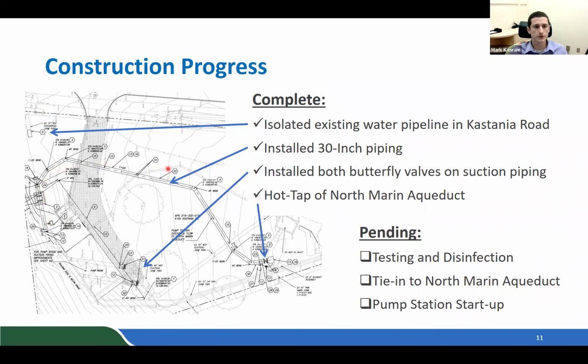Next, we installed roughly 200 linear feet of 30-inch welded steel discharge piping in preparation of connection to the new North Marin Aqueduct. We also installed two 30-inch butterfly valves on the pump station suction piping, and that's located here. And probably one of the more important phases of construction was a hot tap of the North Marin Aqueduct. And I'll describe what a hot tap is a little later. So the pending steps in construction we have remaining are pressure testing and disinfection of our new pipeline, as well as tie-in or connection to the North Marin Aqueduct. And this is the point at which we're fully connected and mechanically prepared to move water. The last step of construction will be electrical testing and then pump station startup.